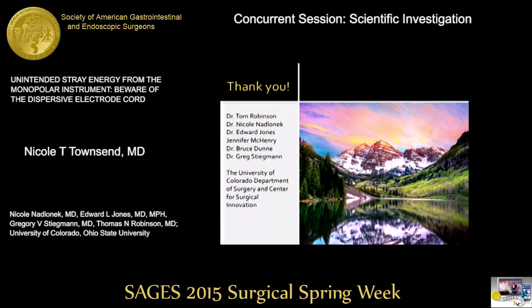While we've looked at those devices in a lot of our antenna coupling studies, we didn't look at that as intentionally in this because we know that ultrasonic and bipolar devices don't contribute to stray energy transfer anywhere near the amount that the monopolar instrument does. But we have confirmed that monopolar instrument use in laparoscopic settings, open settings, any monopolar instrument use is able to participate to this extent in stray energy transfer. Thank you so much. Okay, thank you.